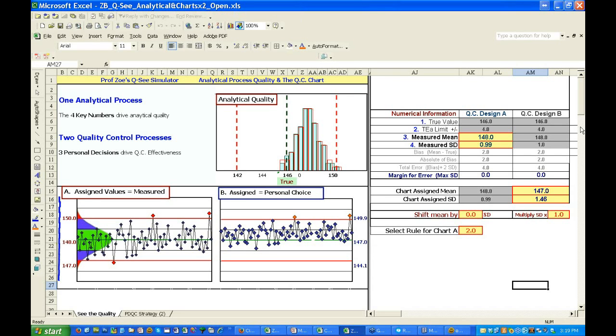But right now, if I walked into this situation, I would say stop. You know, because no result is better than a wrong result, and we're now crossing the total allowable error limits with our results. So we're beyond specifications.